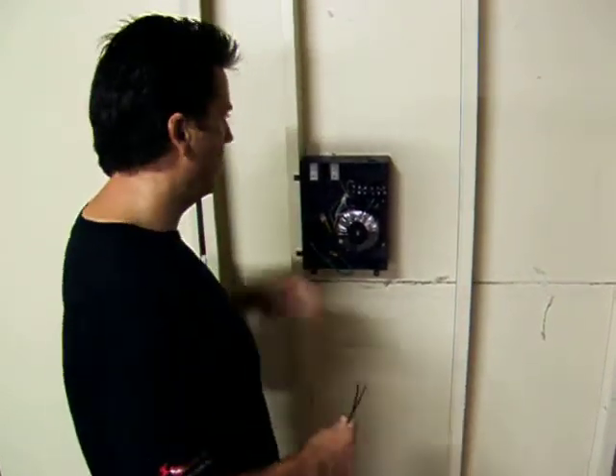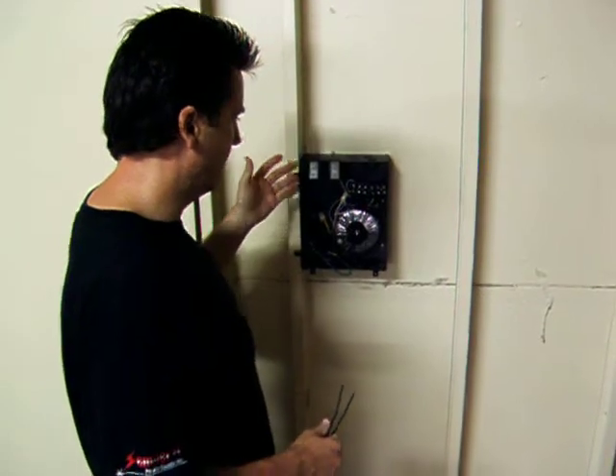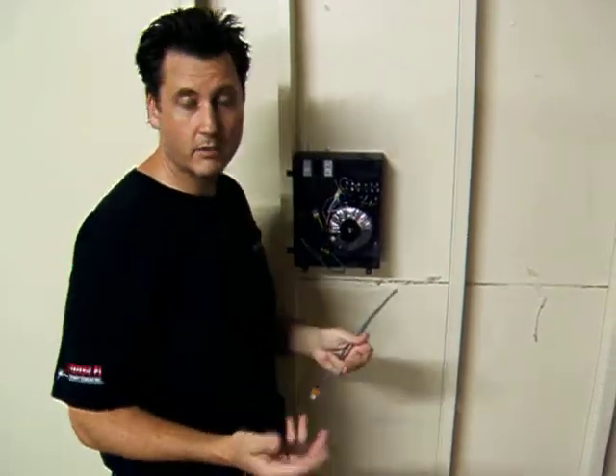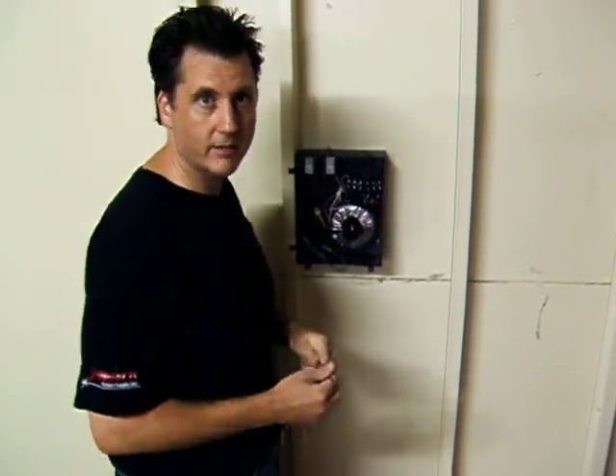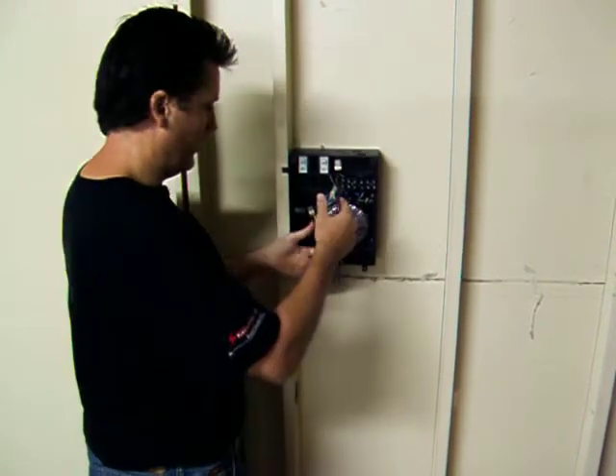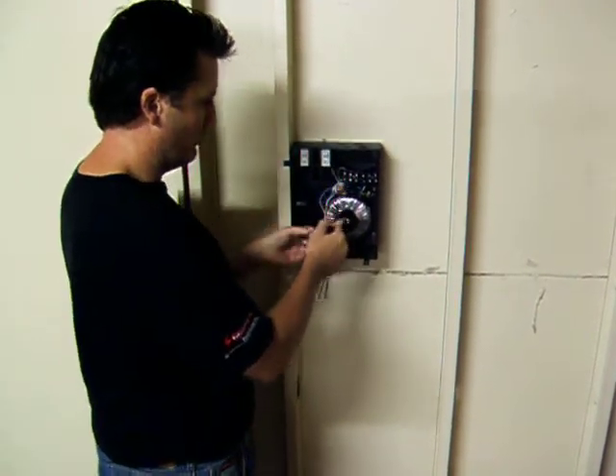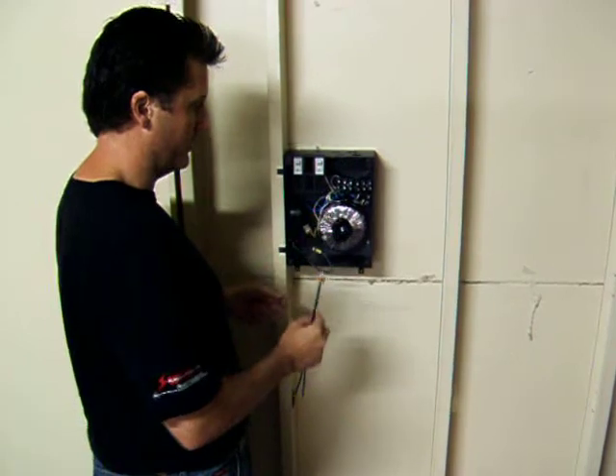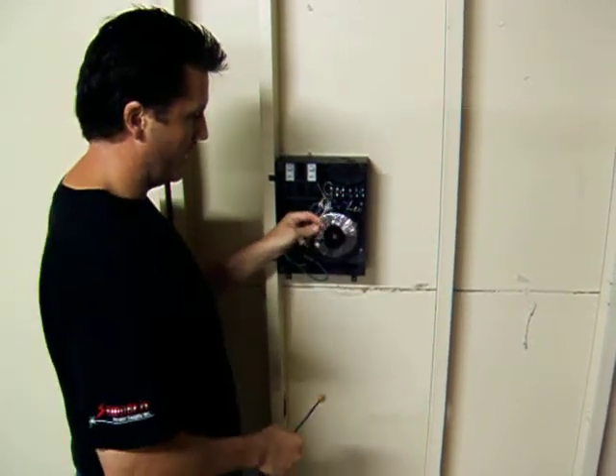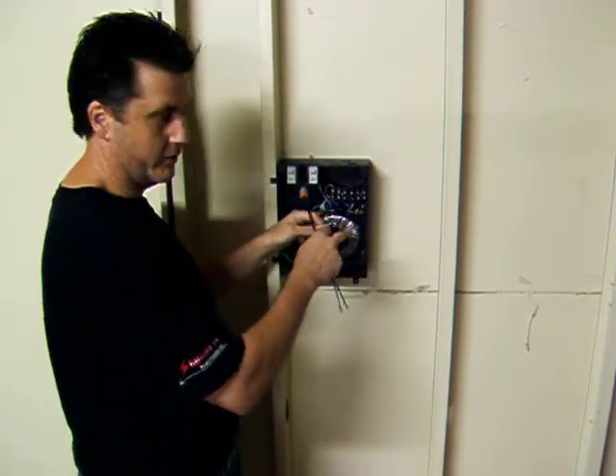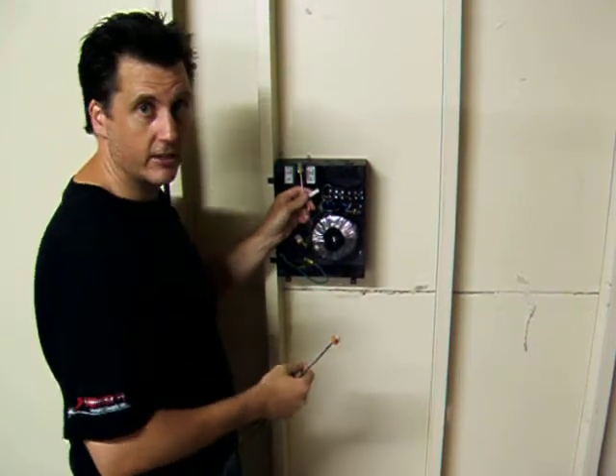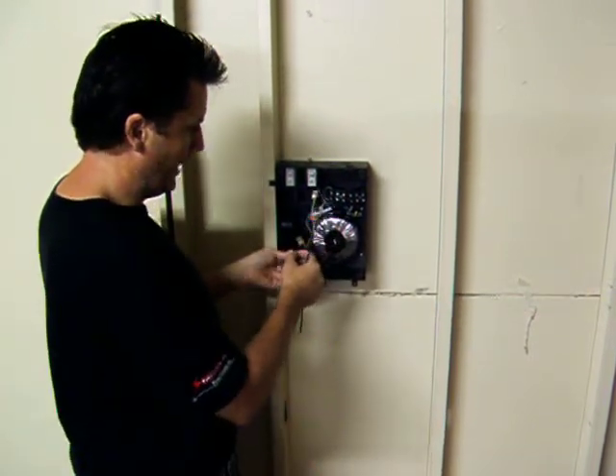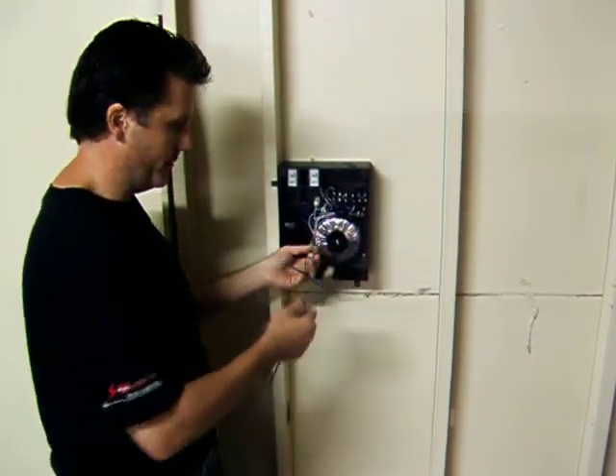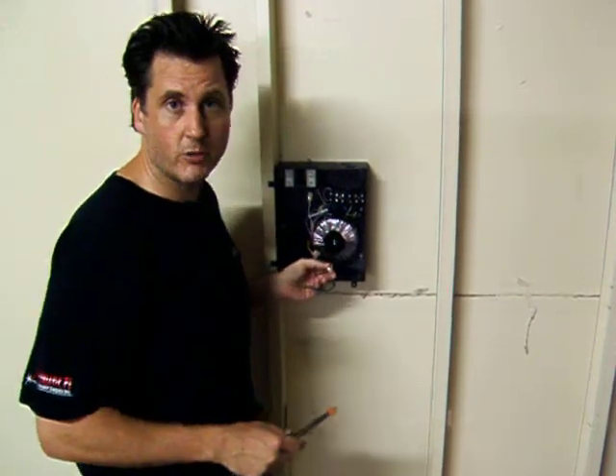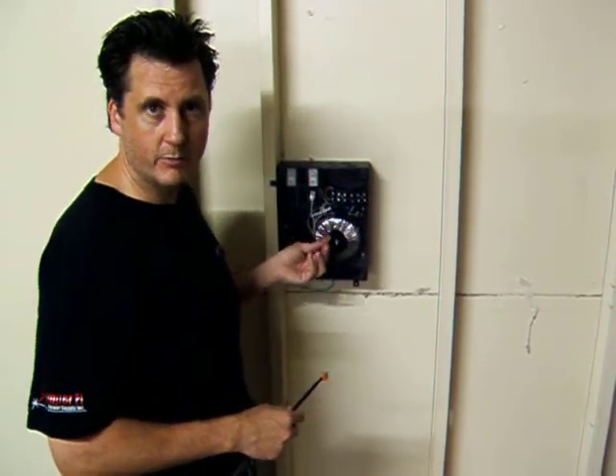So when you have the line voltage coming in, you have two conductors and a ground on the primary side, the line voltage side. And off the transformer, you have three wires, and you have the ground. So you have the white wire, which is labeled 120 volt input here. That's going to take your neutral. And then you'll have a black and a yellow off the transformer. If you're not sure what you need, plug into the black. That's the normal use tap.